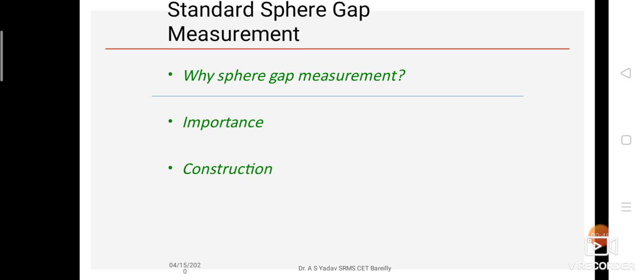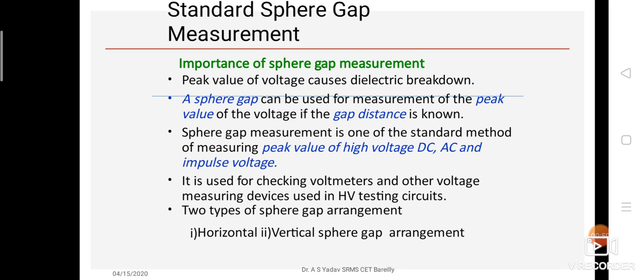Here we are discussing the working of the sphere gap method, measurement of high voltages, importance and the construction of this method. The peak value of voltage causes the dielectric breakdown. A sphere gap can be used for the measurement of the peak value of the voltage if the gap distance is known. The sphere gap measurement is one of the standard methods of measuring the peak value of high voltage, DC, AC and impulse voltage. It is used for checking voltmeters and other voltage measuring devices used in high voltage circuits.